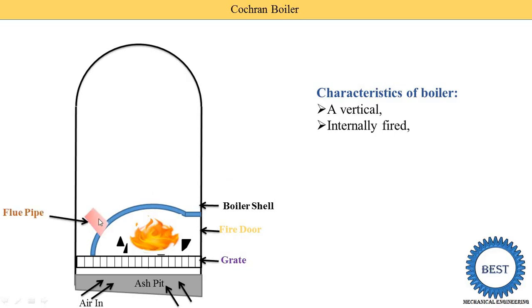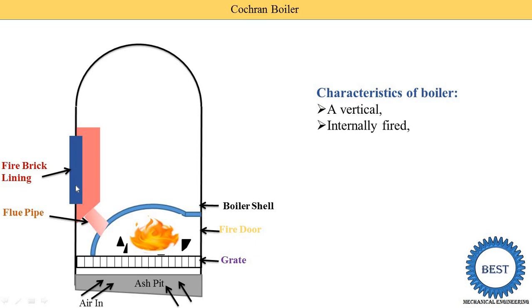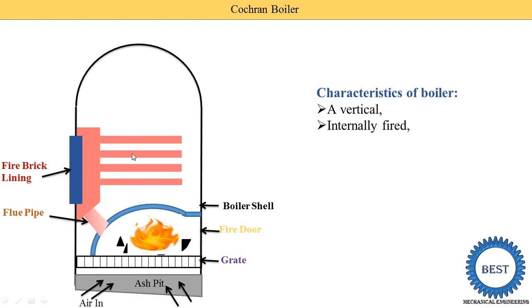The hot gases are supplied to the fire tubes by using the flue pipe. The orange part shown here is the combustion chamber, and it has a fire brick lining. This lining is provided so that heat is not rejected to the atmosphere. From the combustion chamber, different fire tubes are connected. Here we see four fire tubes, so due to multiple fire tubes, one characteristic of the Cochran Boiler is that it is a multi-fire-tube boiler.